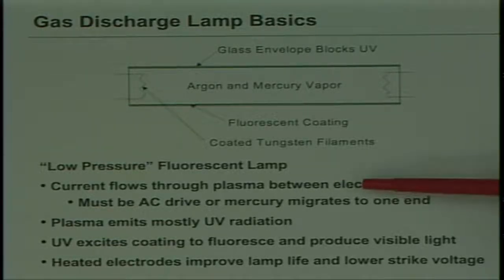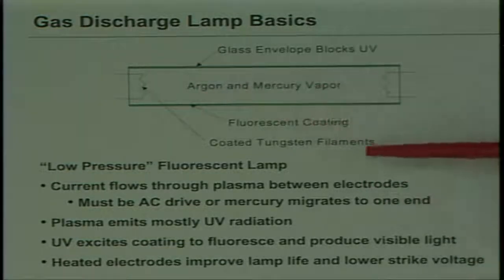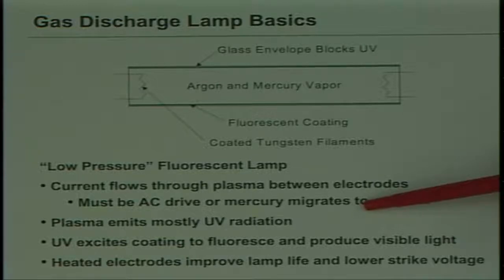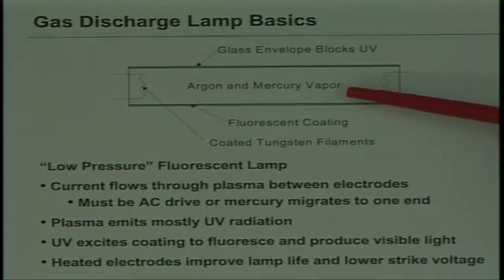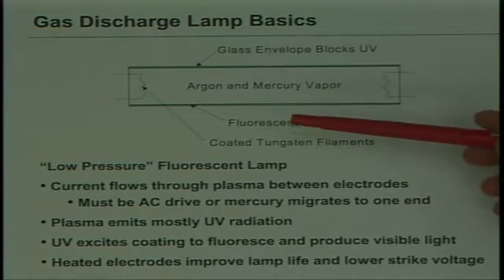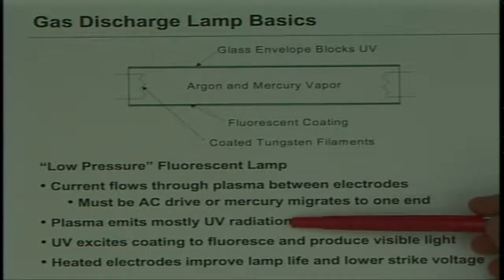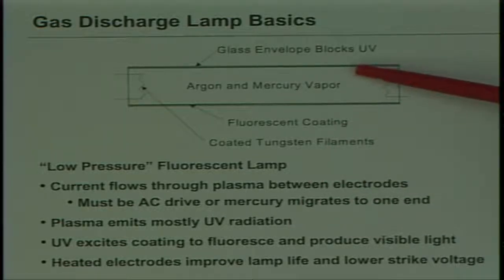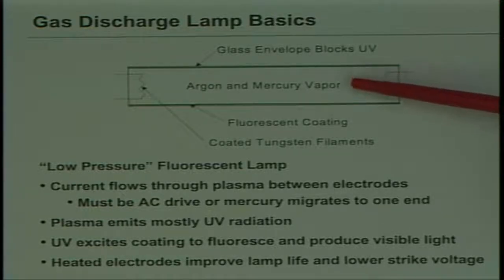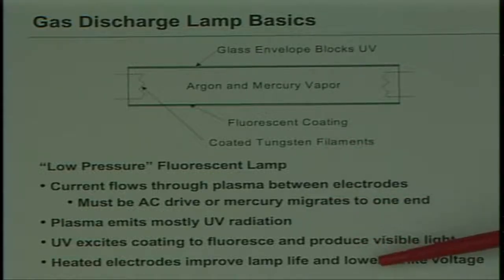When you start these lamps without preheat of the filament, you sputter the material, the tungsten, and you get blackening on the ends of the lamps. Current flows between these two electrodes, basically in a plasma inside the tube. The drive has to be purely AC. If you try to drive this with DC, all the mercury gets pumped to one end of the lamp and it turns into a rectifier and you can't light it anymore. The glass envelope doesn't entirely block UV but it certainly attenuates it. The heated electrodes lower the strike voltage, making the power supply easier, and they also improve lamp life by preventing sputtering.